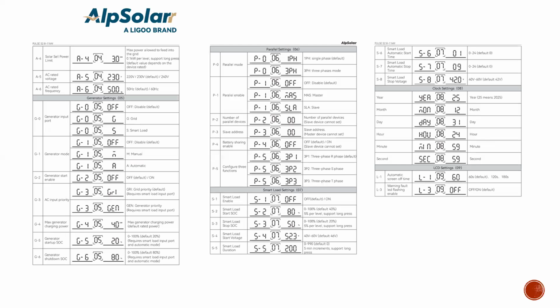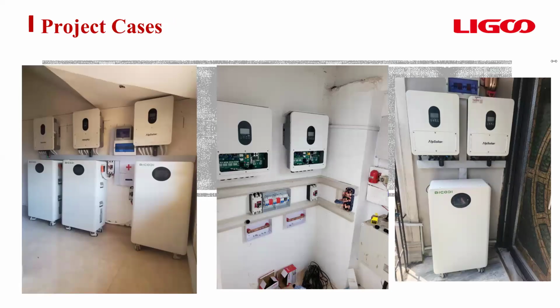Now, let's say you have three inverters in parallel. The first inverter is the master, it's not the slave, so you cannot set slave address for it. The next inverter to the master will be slave one. So under slave address, you put one there, right? And the next inverter under the slave address, you put two there. And then the next thing you are having is battery sharing enable, which you can only set on master. That is where you give the inverters permission to share the same battery bank. So I think that is all I would want to say on the parameter settings.